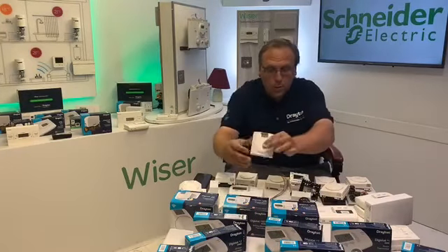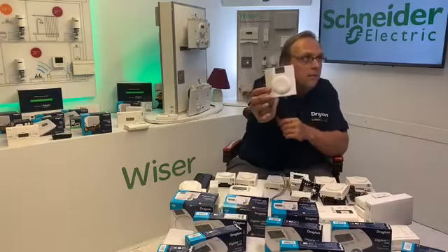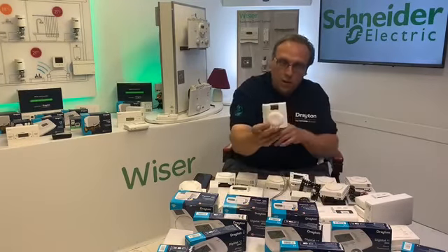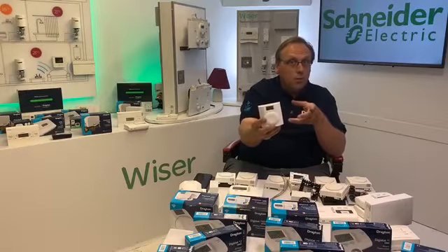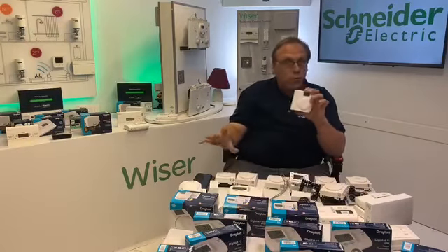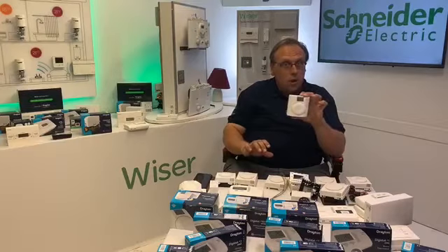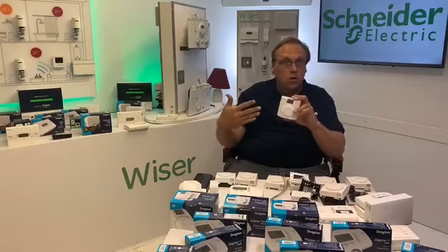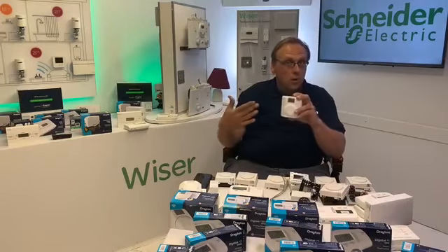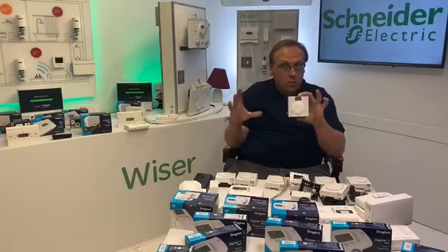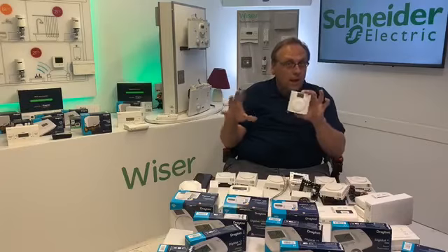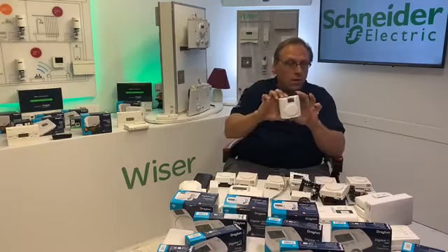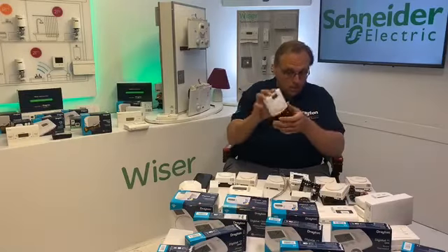So you've probably all seen one of these. This is the Digistat Plus. It's got the dial on the front of it, and this is a straightforward up and down thermostat. So it's ideal to replace something from the RTS range, but it does have intelligence in it, in so much that you can go in and you can control how it modulates. So you can select between the system type between oil and gas, and that will tweak how it modulates the system. So that's what makes it Boiler Plus compliant.